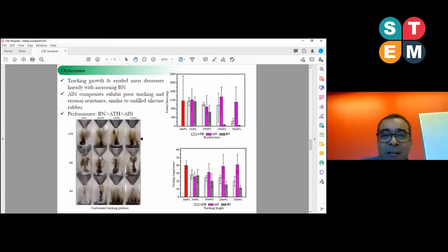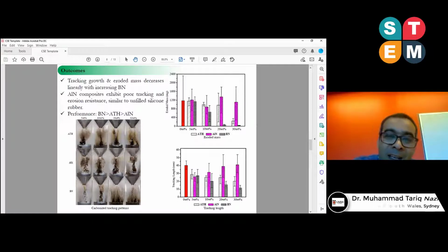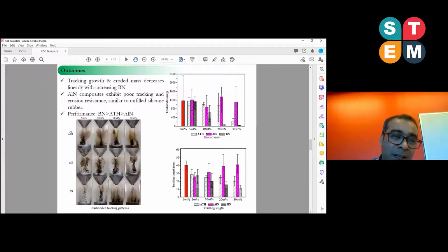At the end of the experiment, that is the situation of the samples with 3 different additives. Here's the top electrode, here's the bottom electrode. This is the carbon tracking; that path is showing the carbonized tracking. Actually, we don't want any tracking because it acts as a conductor, so it reduces the insulation properties sharply. We don't want any tracking on the insulation. So with the three different fillers, ATH, AlN, and BN, we compare the performance. And here we look at the eroded masses.